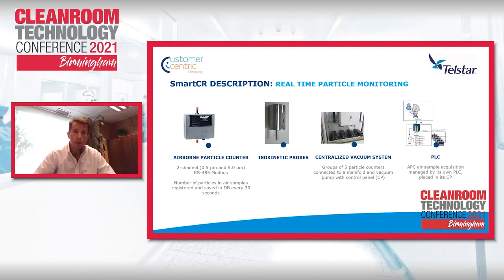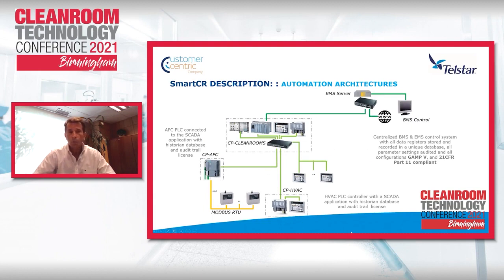Regarding the control system, we have the PLC for the airborne particle counters. We will have the PLC for the HVAC. We will have the common system to control everything related to the clean rooms, such as the HMI in the clean rooms to see the different parameters: particles, pressure, temperature, humidity, whatever. We will also have interlocks, or if the facility is provided with door open detectors, they will be here also in the clean rooms. And obviously, this will be connected to the BMS or EMS, the central BMS or EMS of the facility. Obviously, everything GAMP 5 and 21 CFR Part 11. That is obvious.